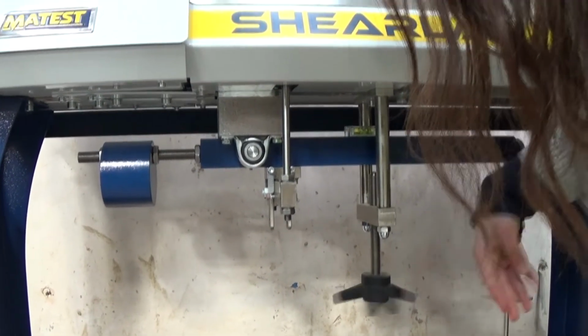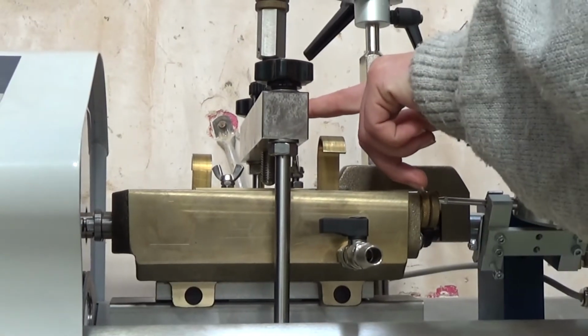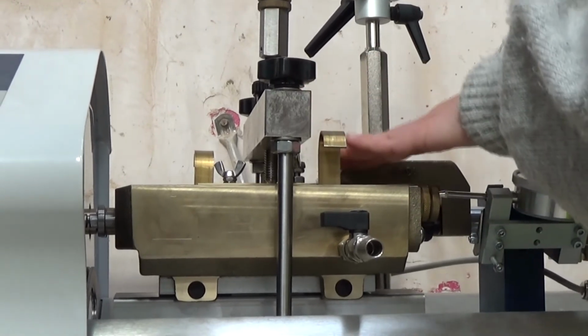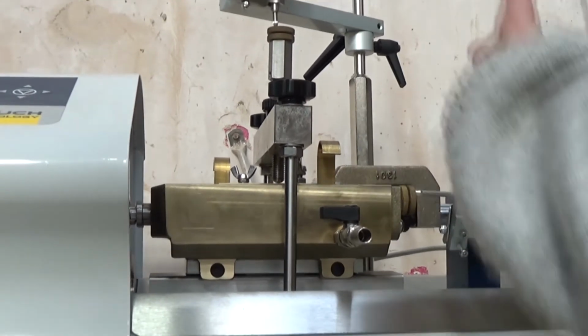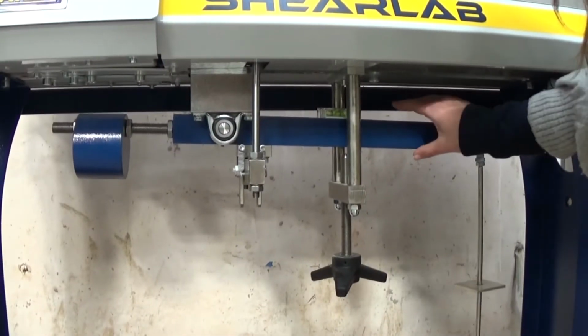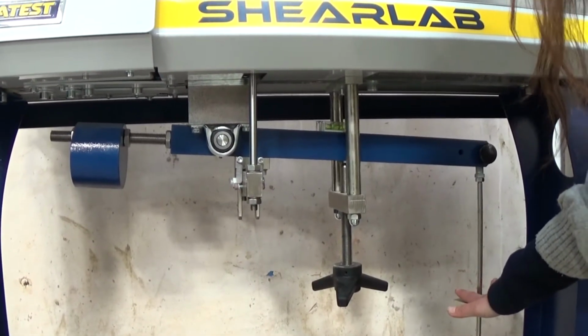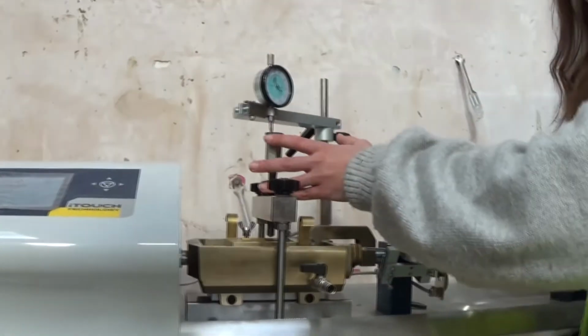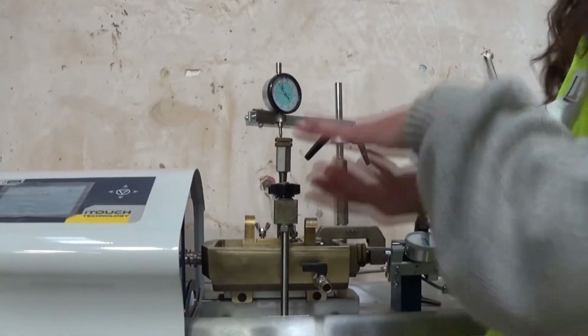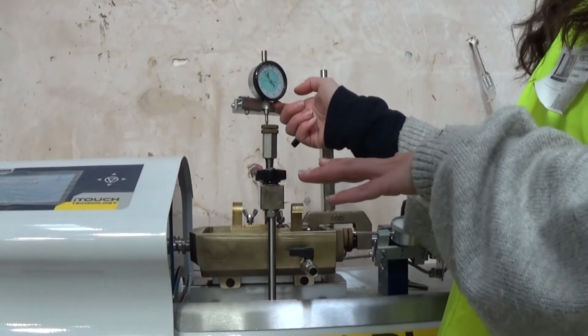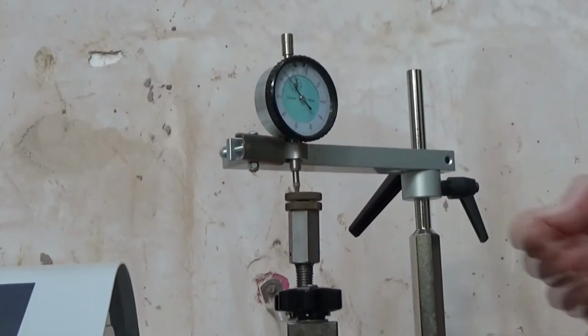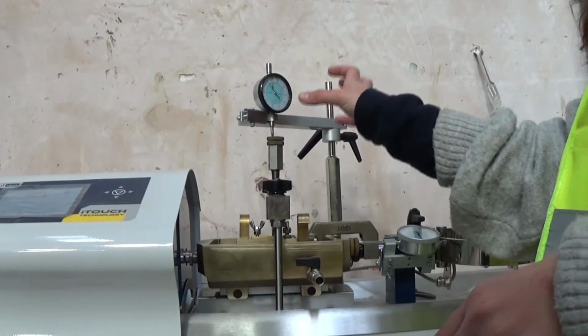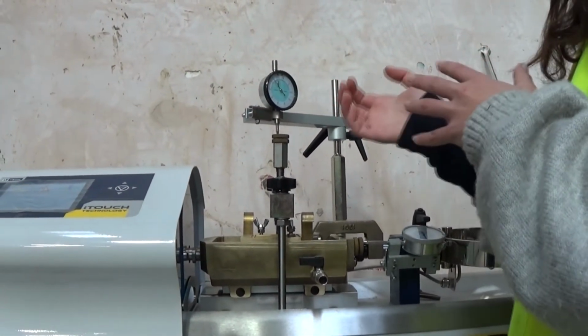and as you can see, also with that weight, if I move the lever, the plate here is moving. It means that it's applying a load. Now it's fake, but the logic is the same. You will apply a load that will move the lever and will apply the load to the sample. And for sure the sample will compress and the dial gauge will extend. You have to adjust it so that you can start from zero.